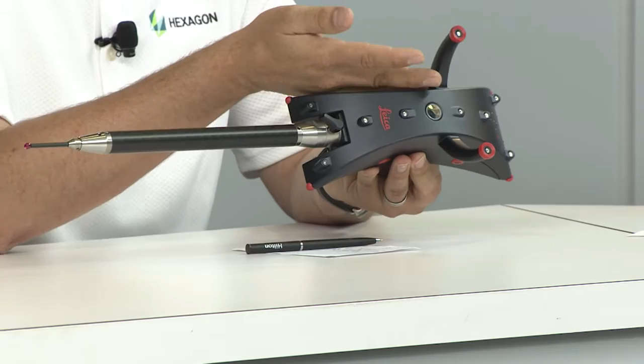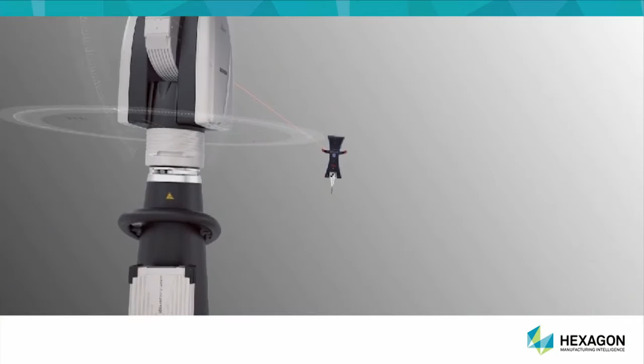Where the T-probe has an advantage is that we're actually measuring at the stylus, at the tip of the probe. So the laser tracker sees the head of the probe, but the measurements are being done at the tip of the probe. Okay. So if I needed to measure something down here on the floor, I would have that ability with the laser still tracking to the prism rather than trying to track to the end effector. To do it, as I mentioned, we have a prism in the center of the probe, and we have a series of LEDs. And we're using two combined technologies. We're using the traditional laser tracker, the interferometer, to measure to the prism, and then we're using photogrammetry with the camera to measure to the LEDs. I've got another video that we can bring up quickly that is sort of the way that the T-cam measures on these LEDs.